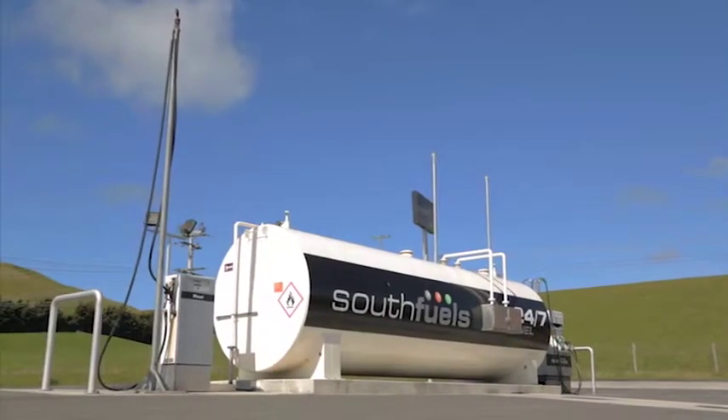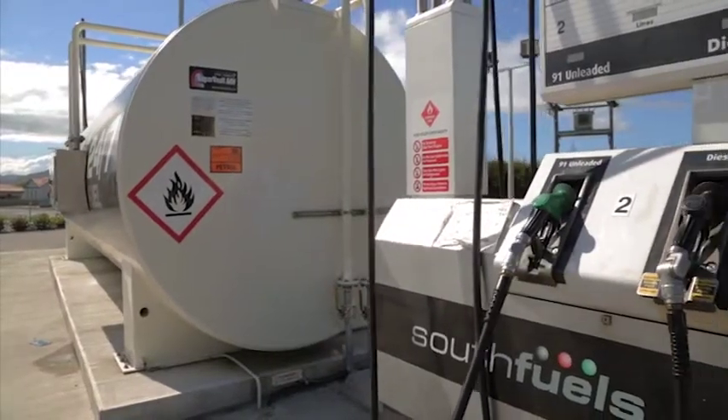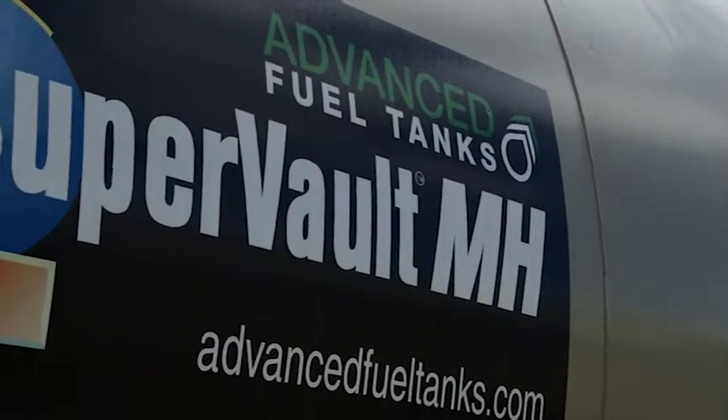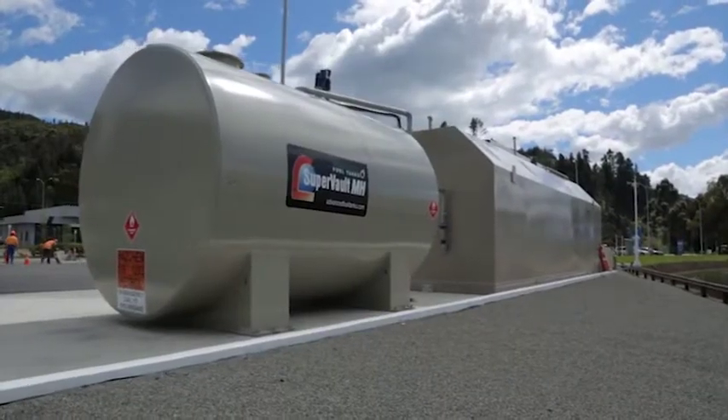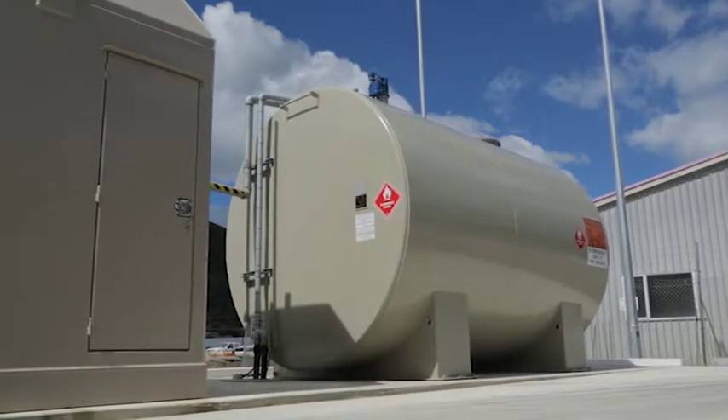Advanced Fuel Tanks also have the exclusive licence to manufacture the US-designed SuperVault for all territories outside North America. A SuperVault tank is a double-bunded tank, but it also has a unique insulation between the two skins that makes it resistant to fire for four hours. It's the only tested and approved four-hour fire resistant tank in the world.